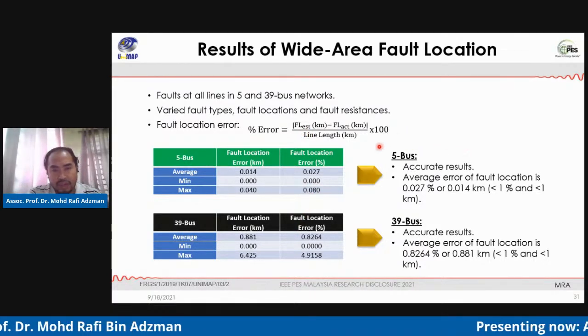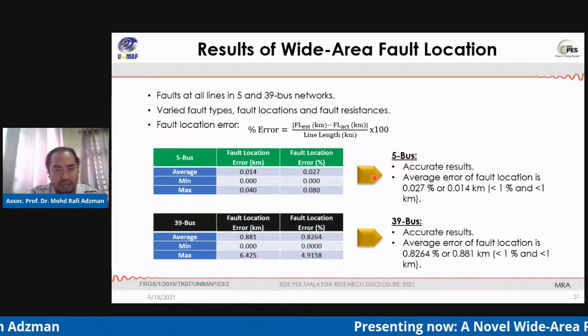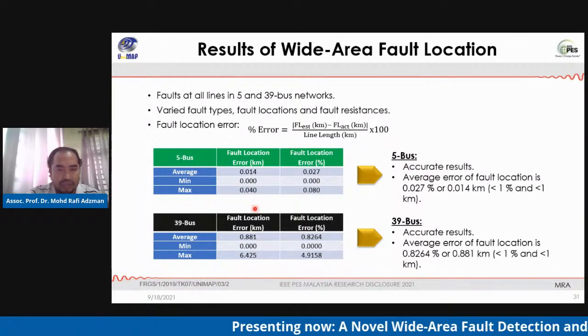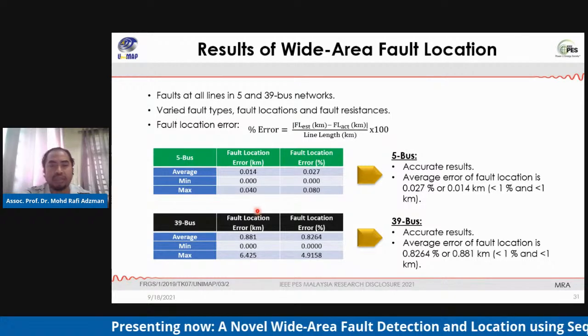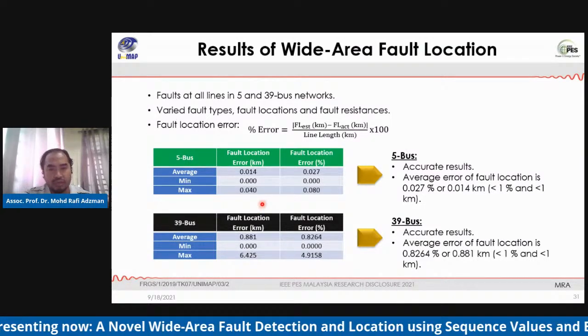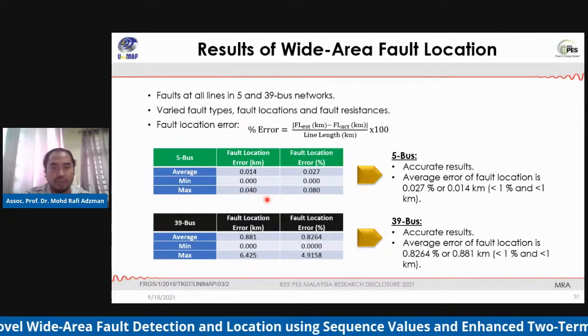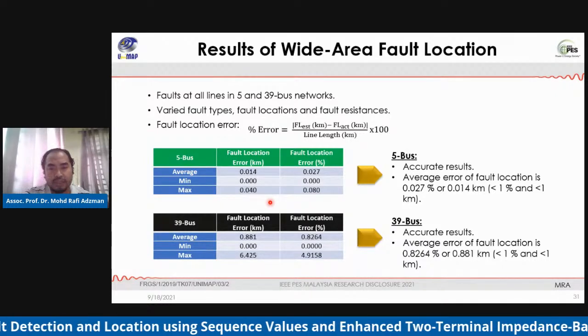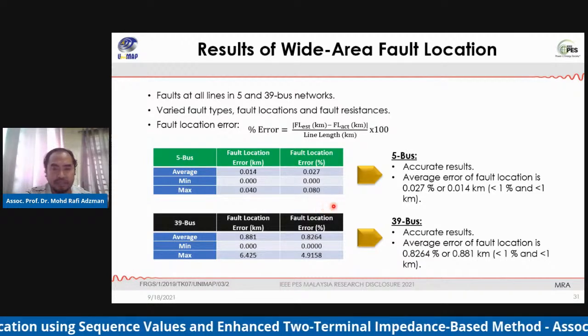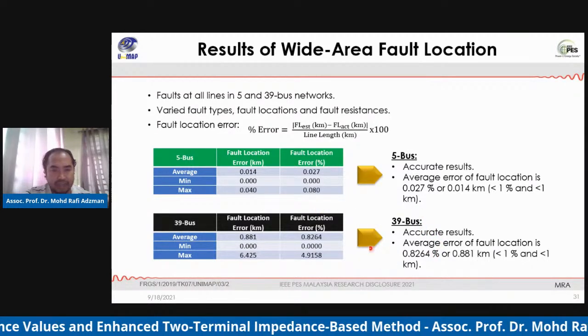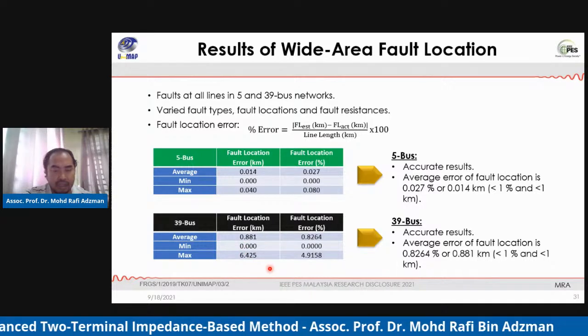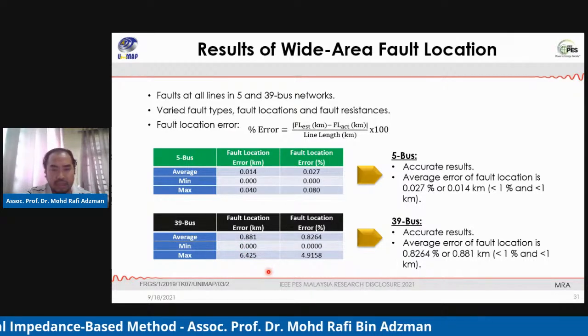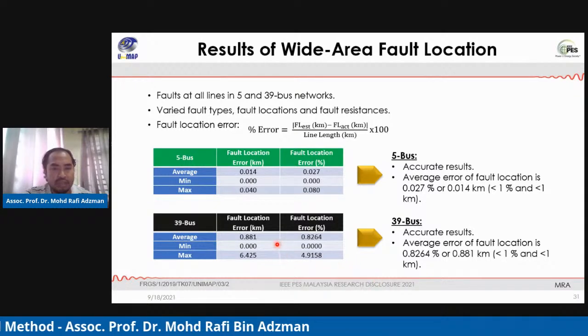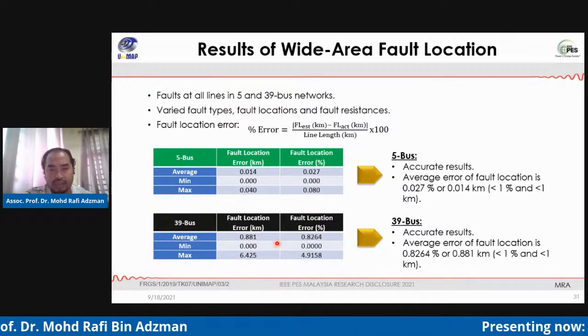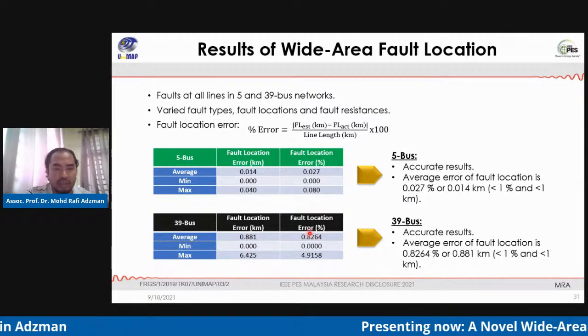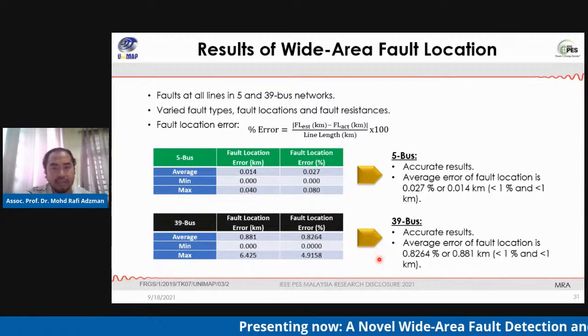For example, here the 5 bus shows accurate results. The average error of fault location is 0.027%, or equal to 0.014 kilometers, which is less than 1 kilometer. For the 39 bus, we can see that the result is quite good, and the average error of fault location is 0.826%, or equal to 0.8 kilometers, which is less than 1 kilometer.